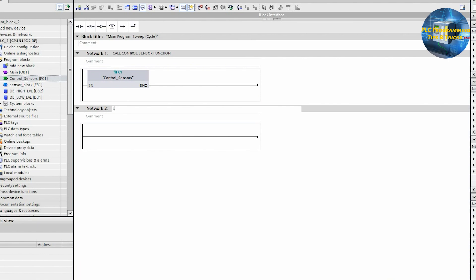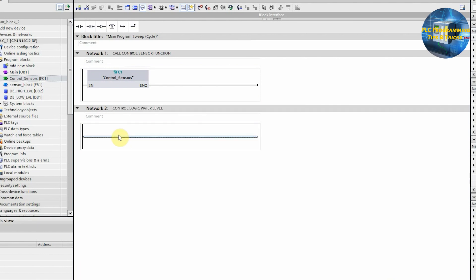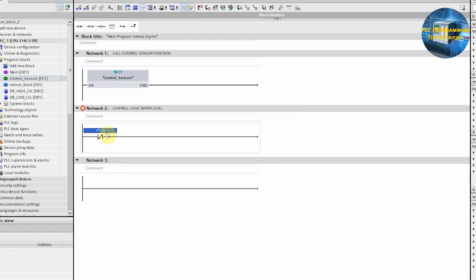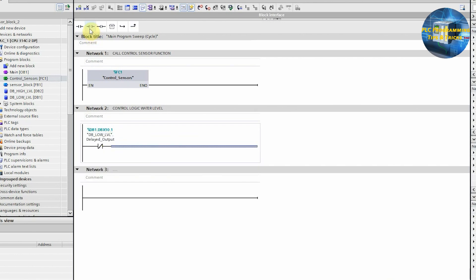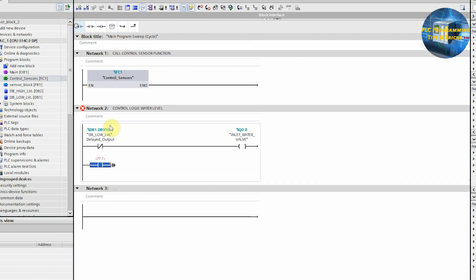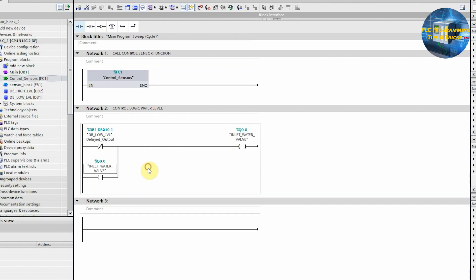Next, in network number two, we will insert the normally closed contact of the low level delayed output. Then we will insert an output coil and assign it Q0.0 — the inlet water valve. Next, we will make the hold-on logic for output Q0.0 by inserting a normally open contact of Q0.0 in parallel, so that when the water level goes below the low level sensor, output Q0.0 gets latched on.